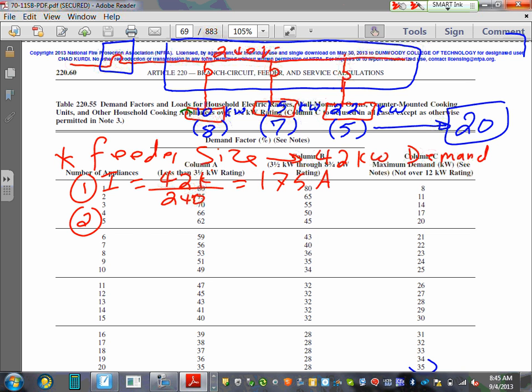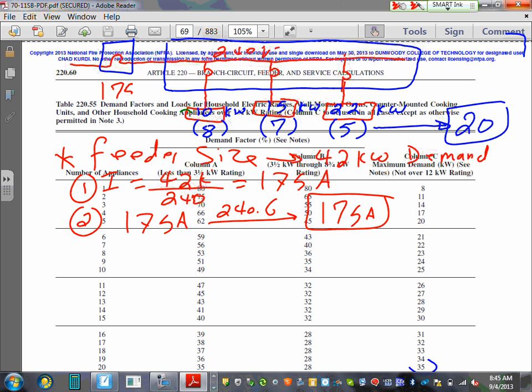Step number two, my friends, is you take the 175 amps to 240.6 in the NEC code book to find the standard overcurrent protection. Everybody knows that. If you don't know that 175 is the standard, you go to 240.6. It will tell you all the standard non-adjustable circuit breakers that we use in the US. 175. So the circuit breaker is already sized. This will be a 175 amp, 2-pole circuit breaker. Done. Go buy yourself a panel at 175.